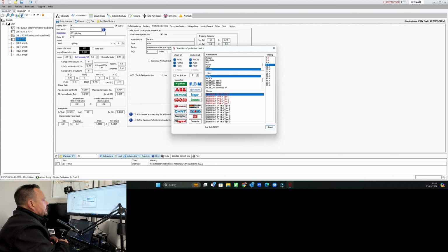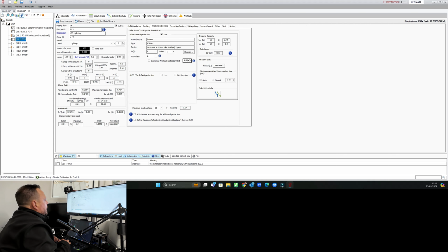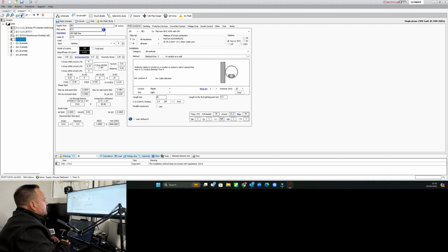So again, we're going to have Proteus. Again, we'll have an RCBO. We'll go for a C-type. And this time, we'll select a 10 amp just to give us a bit more. Well, let's keep it at 6. Why not? We'll keep it at 6. So we don't need fault protection on that. It's not asked us for the warning because it's not a socket as such. But we've got that there, and there's no warning shown.